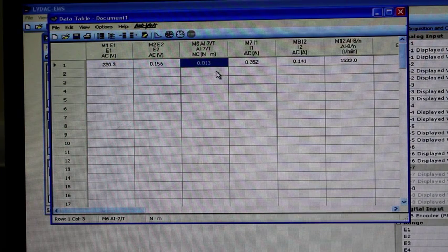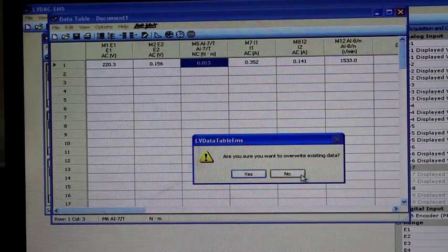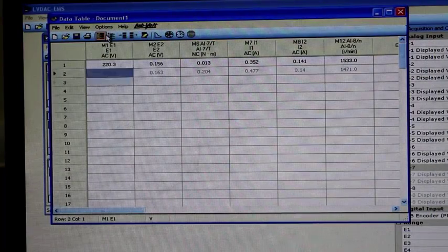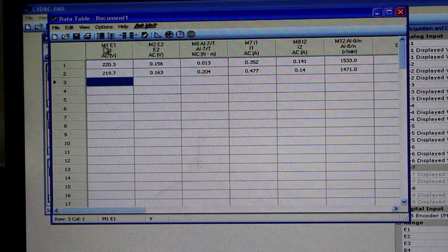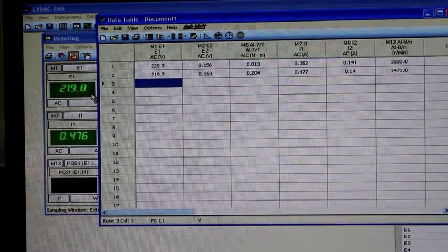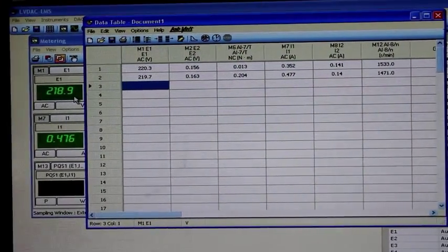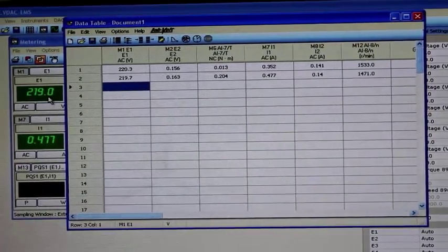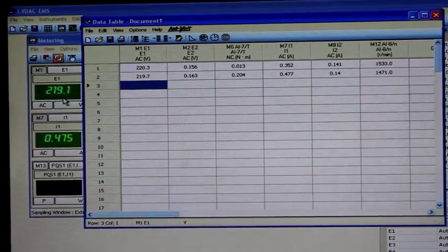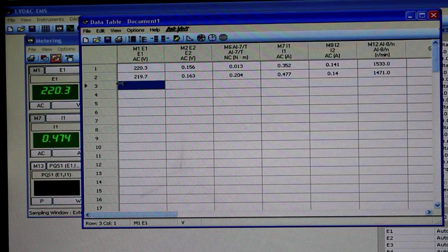It's almost zero right now. So let's make it 0.2. Increase by 0.2, same like we did in the separately excited, as mentioned in the report manual. Now, the voltage will decrease a little bit. Keep following up the voltage. Make sure that it stays at your selected value, 220. When you increase the torque, the voltage decreases a little bit. Just increase it from the voltage control knob to make sure that it doesn't stray away from your required value.